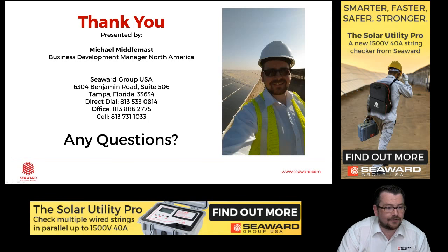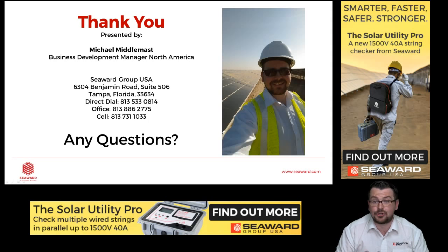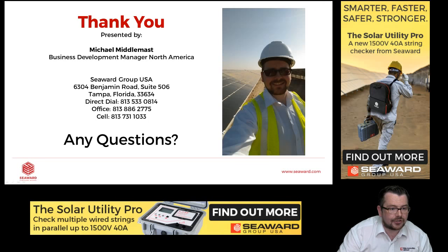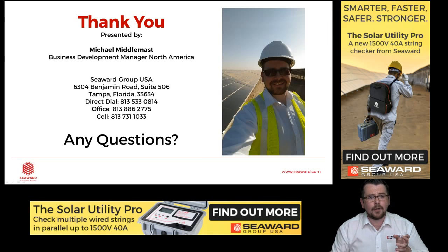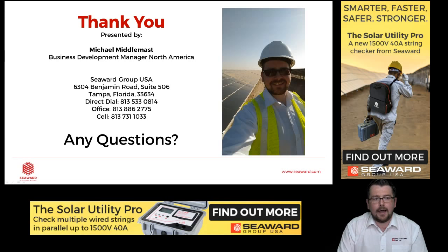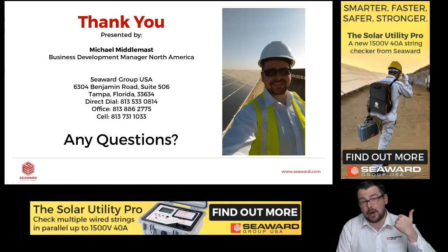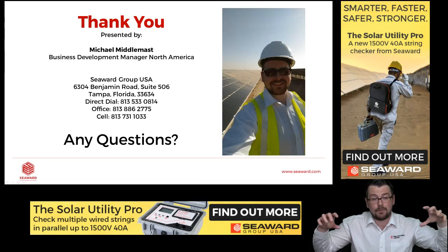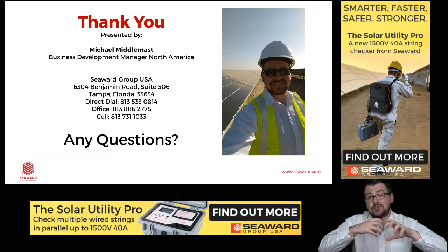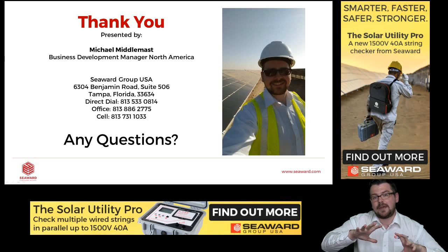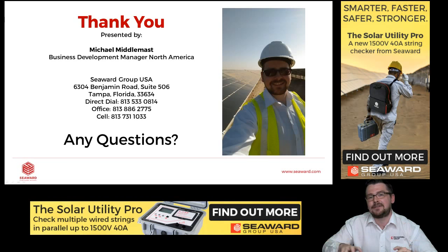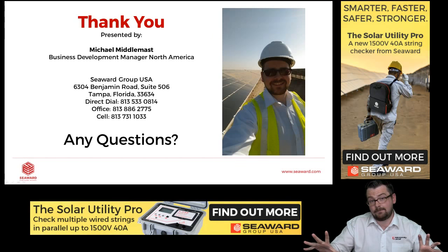Stephen Bale says, I've used the PV150 to test installations through a string. However, when the panels were covered in snow or shade, we get low readings. Is this what's happening inside the string or the panels, or is this what is causing this low insulation resistance value? I would really test when the panels are clean. Okay, that means no snow as well. It also could mean what I mentioned quite earlier in the presentation, that we may have moisture in the connections and that's causing an insulation fault. So I would make sure that you're only testing insulation resistance on a clean, dry array.